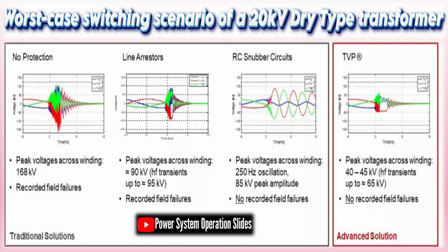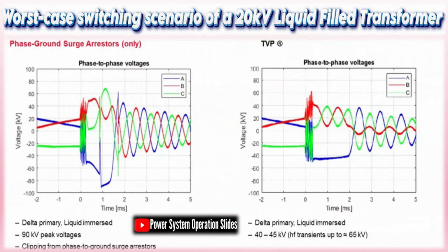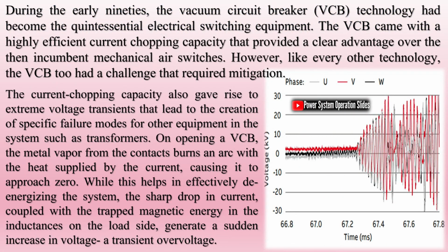During the early 90s, the vacuum circuit breaker (VCB) technology had become the quintessential electrical switching equipment. The VCB came with a highly efficient current chopping capacity that provided a clear advantage over the then incumbent mechanical air switches. However, like every other technology, the VCB also had a challenge that required mitigation. The current chopping capacity also gave rise to extreme voltage transients that lead to the creation of specific failure modes for other equipment in the system such as transformers.